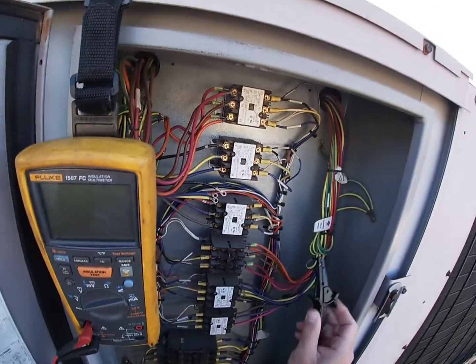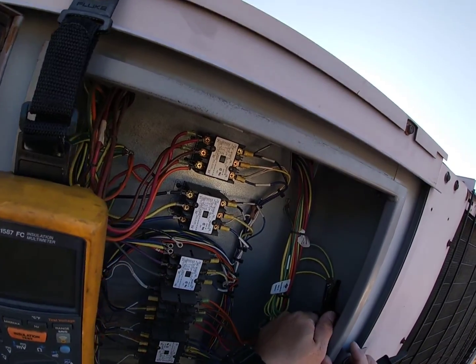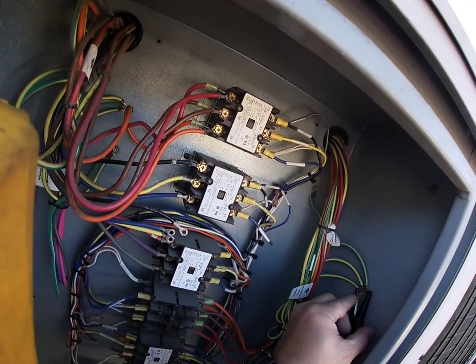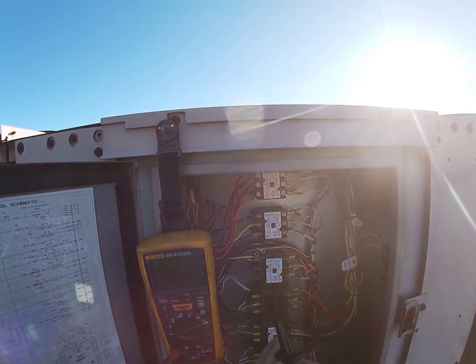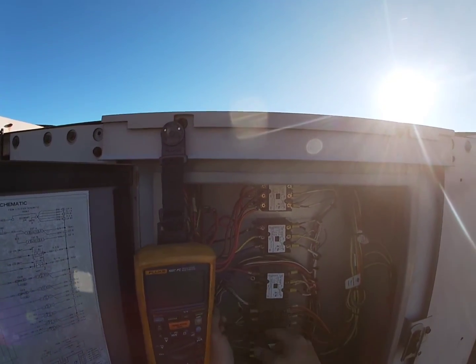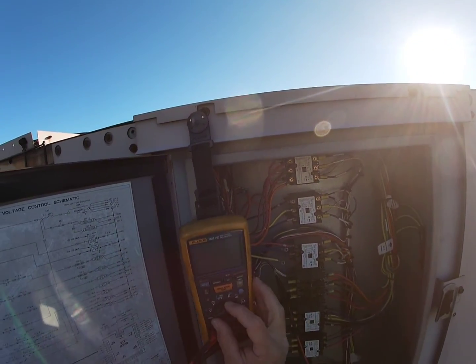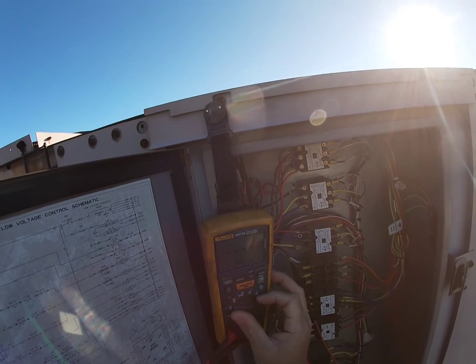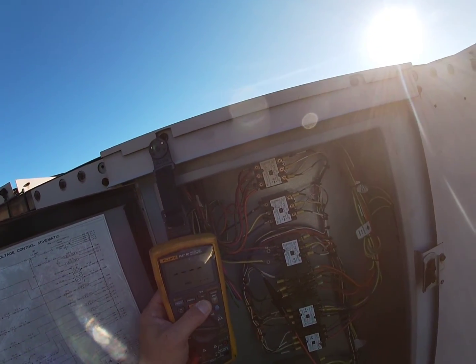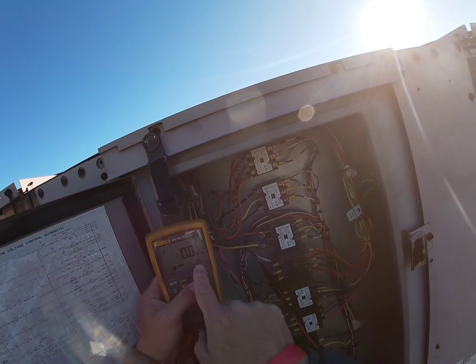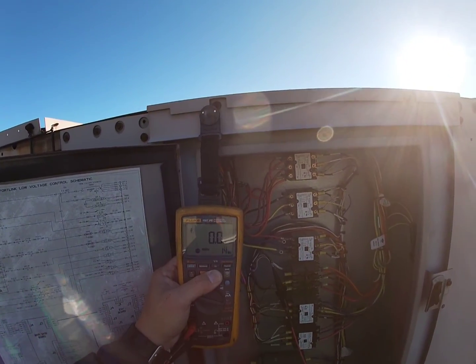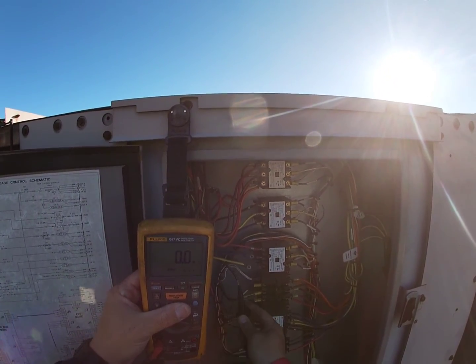Put that on a good known ground source. Obviously that's one right there. I'll go ahead and put this on that lead right there and test that at 500. As you can see, it's not taking my voltage, showing 0 mega ohms, so that's bad.